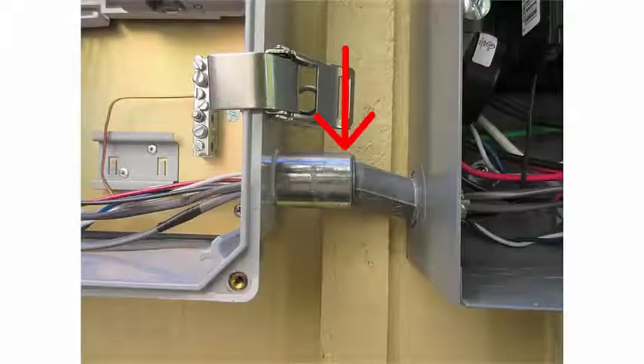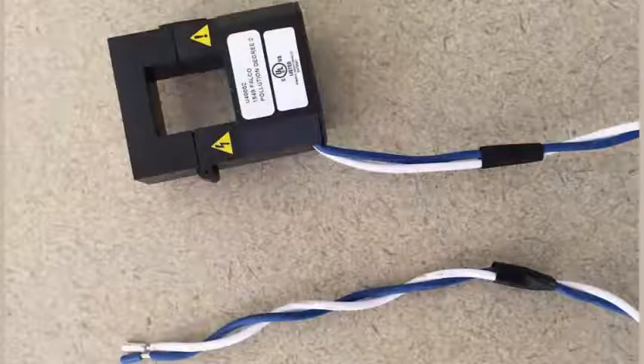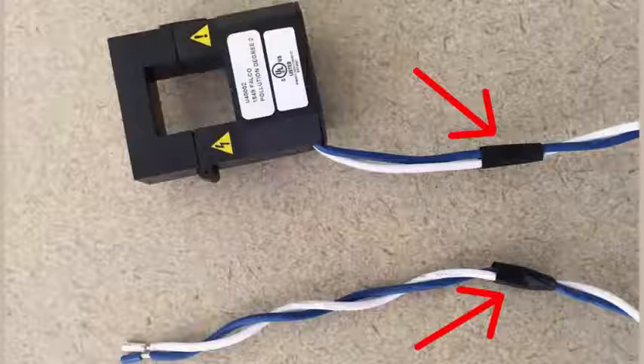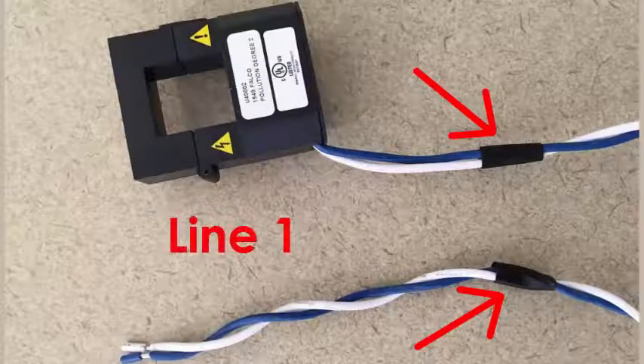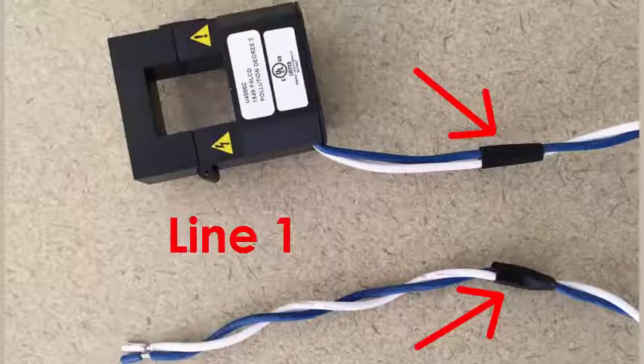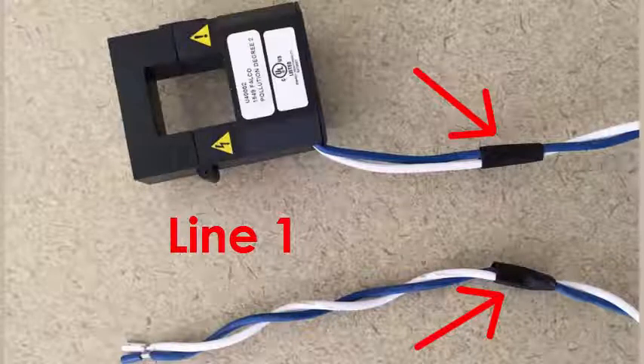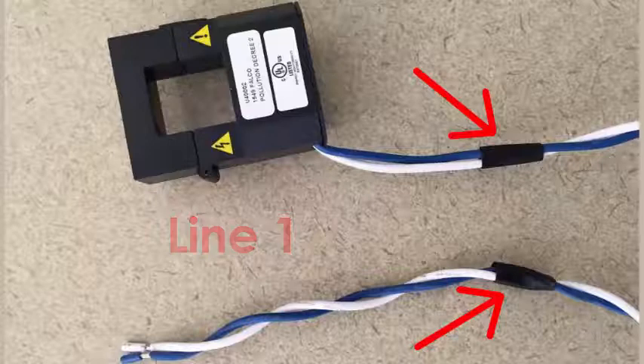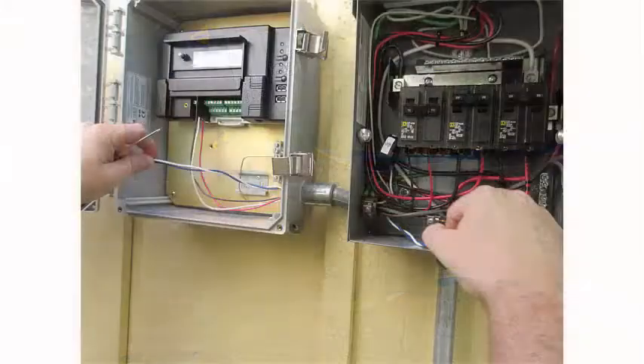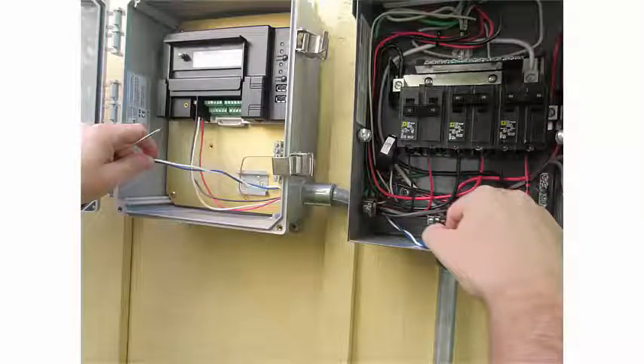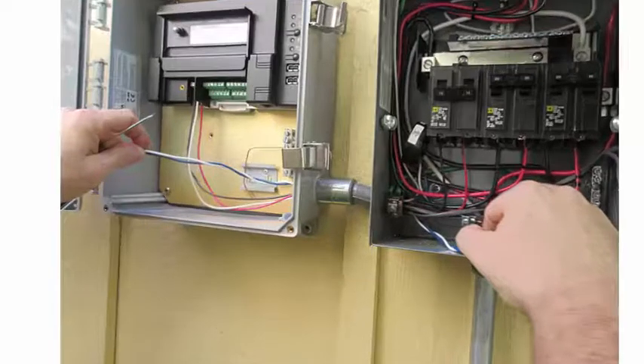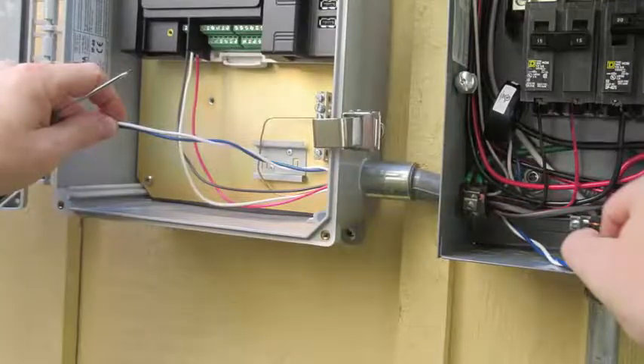Create a protected route using conduit for the CT wires from the main load center to the Envoy S. Before running the CT wires through the conduit, use black tape to mark both ends of one of the CTs. You will use this for line 1. Marking the line 1 CT will enable you to correctly match both CTs for lines 1 and 2 between the Envoy S and the main load center. Run CT wires through the conduit to the Envoy S. Because the CT wire voltage is rated for 600 volts, you can use the same conduit as the power conductors and pull all of the wires through the conduit at the same time.